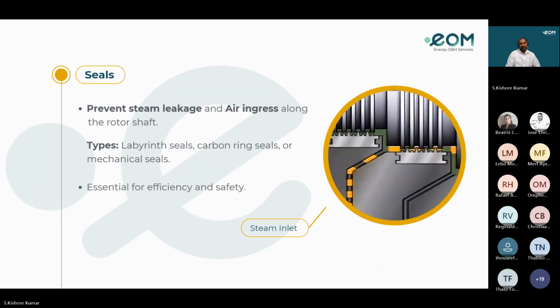Gland seals. Coming to the gland seals, they play a critical role in steam turbines, especially at the points where the rotating shaft exits or enters the turbine casing. The gland seal ensures steam does not leak out of the casing and air does not leak into the turbine along the rotor shaft. This is especially important in the low pressure section where vacuum may be present. The types are labyrinth seals, carbon ring seals, or mechanical seals, and they are essential for efficiency and safety.